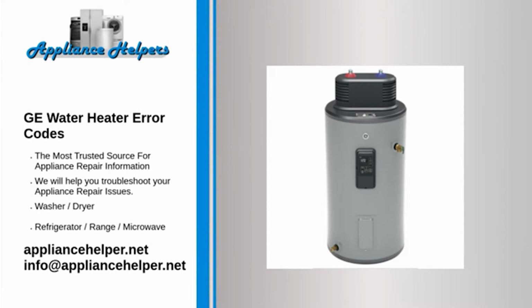If you're looking for help fixing your GE water heater, look no further. Our comprehensive GE water heater error code guide will explain common issues, provide tips, and show you how to read your model's error codes. Code FA. Problem: compressor discharge temperature not rising. Fix: the T4 sensor, compressor outlet temperature sensor, must detect at least a 20-degree temperature rise during the first 30 minutes of runtime.